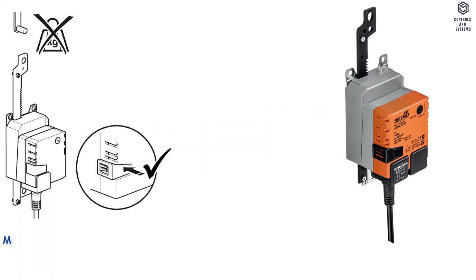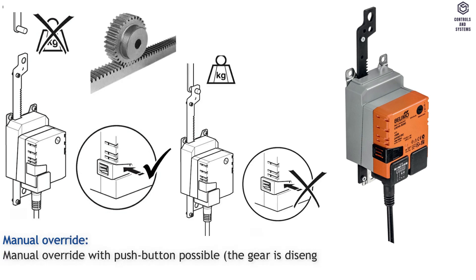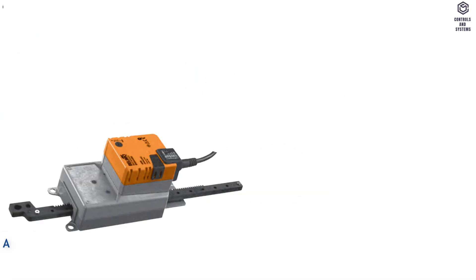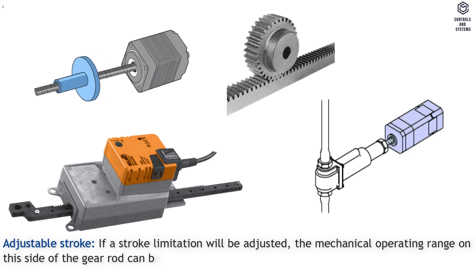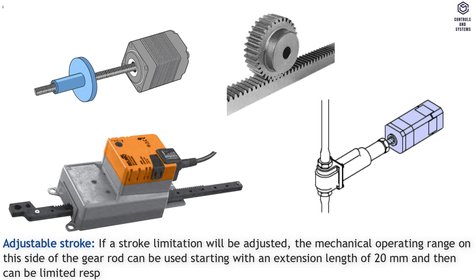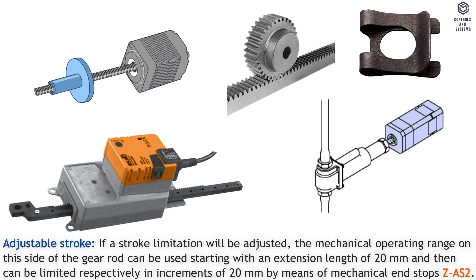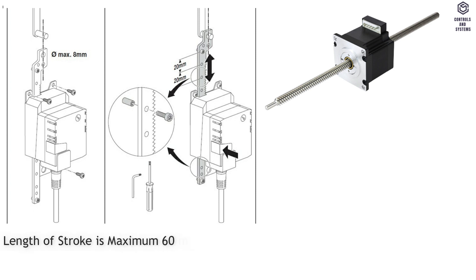Functional data. Manual override with push button is possible; the gear is disengaged for as long as the button is pressed or remains locked. Adjustable stroke: if a stroke limitation will be adjusted, the mechanical operating range on this side of the gear rod can be used starting with an extension length of 20 millimeters, and can be limited in increments of 20 millimeters by means of mechanical end stops Z-AS2. Length of stroke is maximum 60 millimeters, adjustable in 20 millimeter increments.